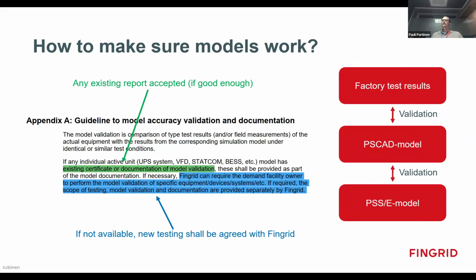And the intention is to conduct factory tests, and then the PSCAD model is validated against the test results. Then the PSS/E model can be validated against the test results or the PSCAD model. This is something that we also are formulating at the moment, this necessary test list for model validation. And this was basically everything I had to present.